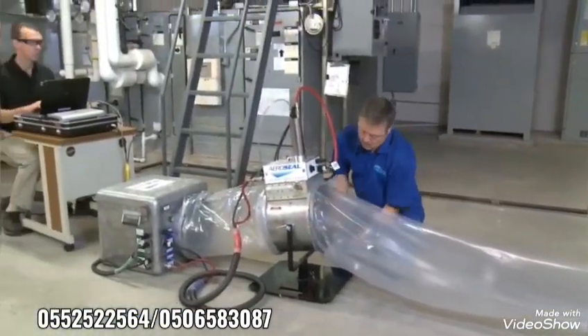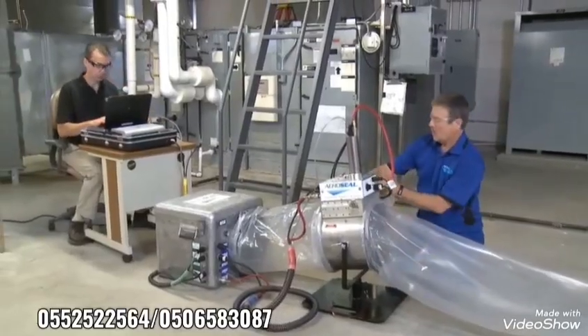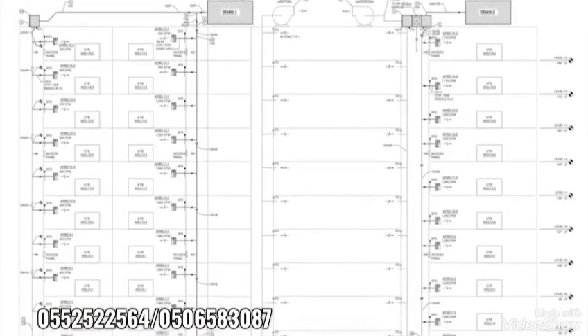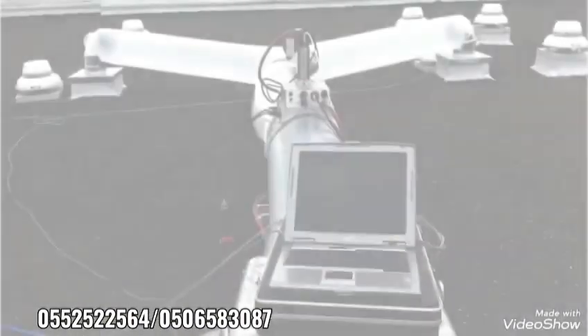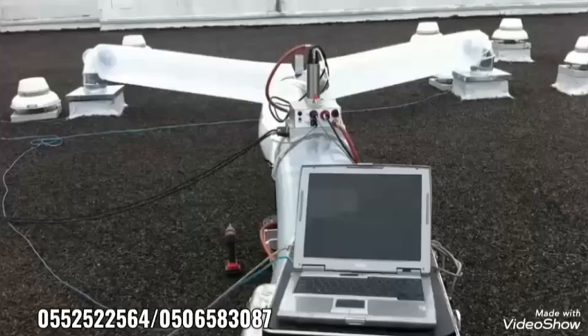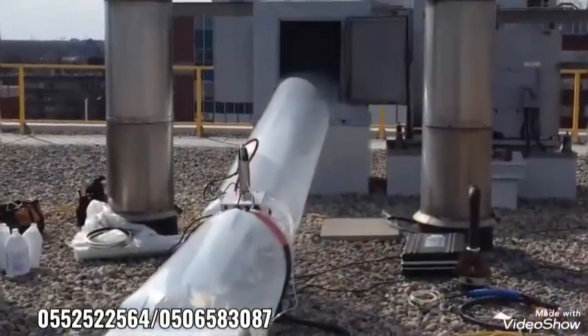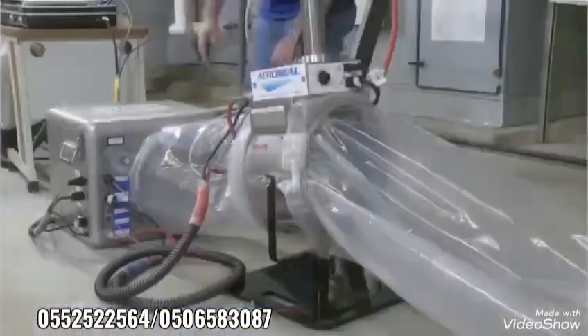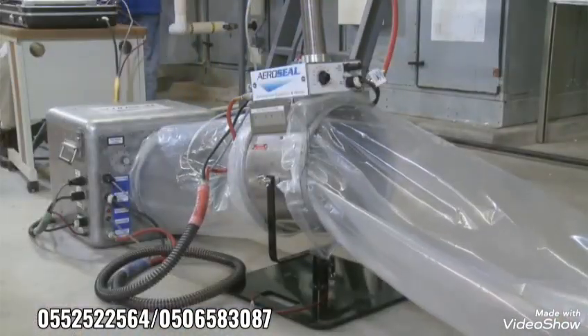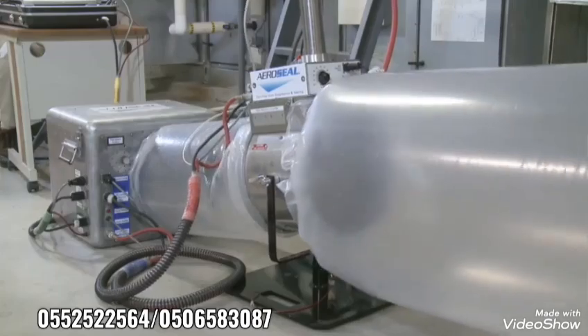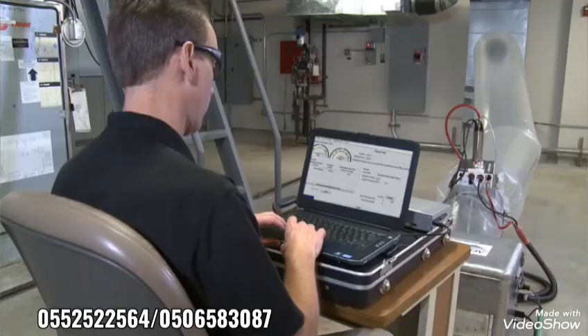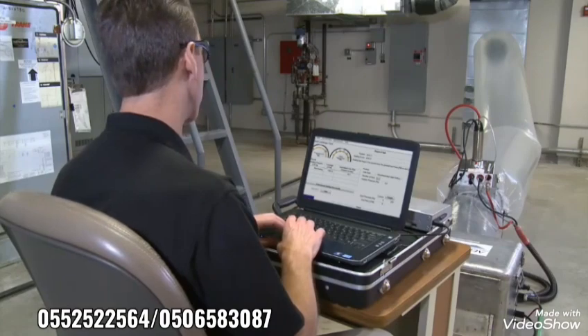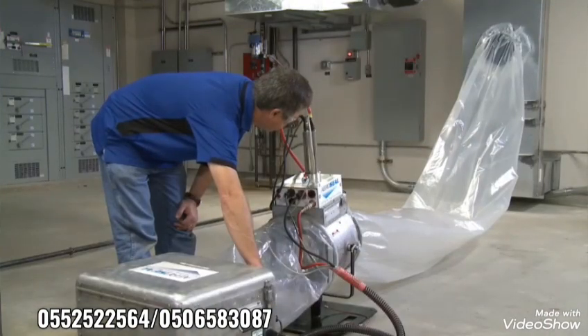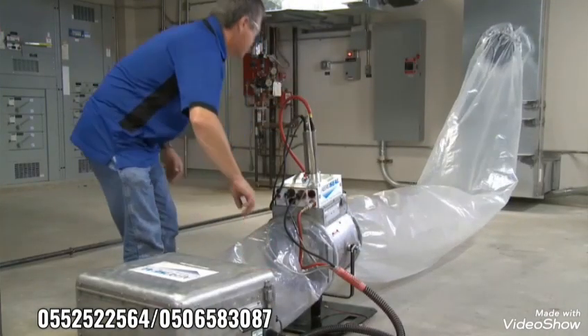There are typically multiple injection points in most commercial duct sealing projects, at least one per vertical riser and at least one per each main horizontal trunk. There is no limit to the size or length of duct to be sealed. In some cases, the equipment is operated from the roof. Now that the equipment is assembled and connected to the ductwork, a pre-seal static pressure test is completed. The result is displayed on the computer screen. With the pre-seal leakage rate recorded, the actual sealing process can begin.